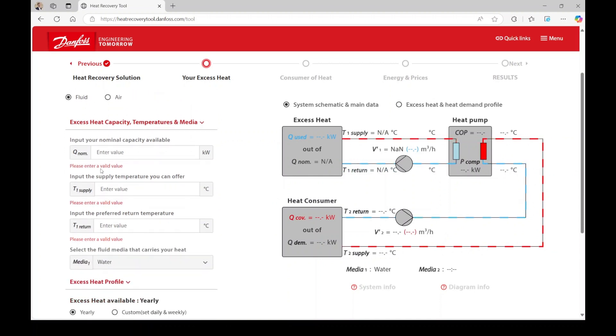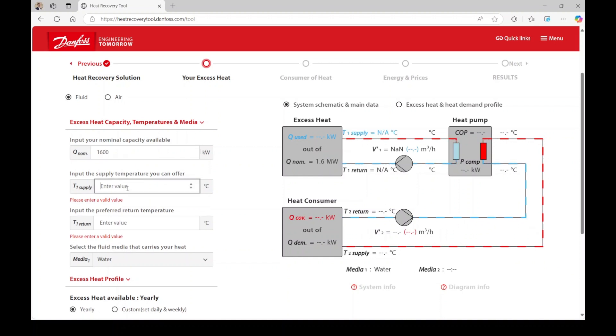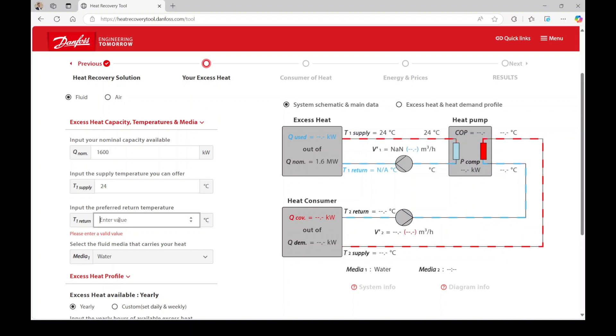Next, enter the capacity of your excess heat source, along with the supply and return temperatures. For our example, the excess heat capacity is 1,600 kW, the supply temperature is 24 degrees Celsius, and the return temperature is 16 degrees Celsius.